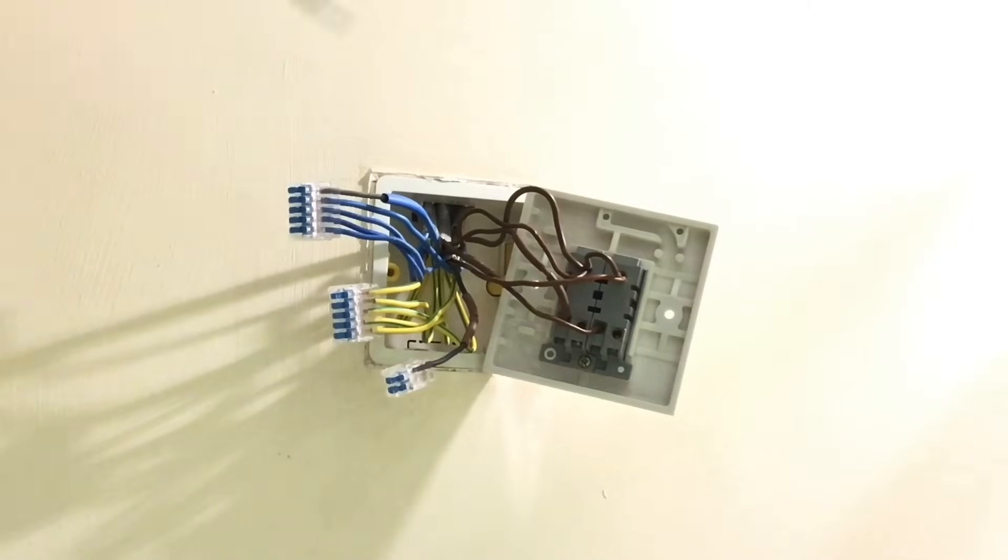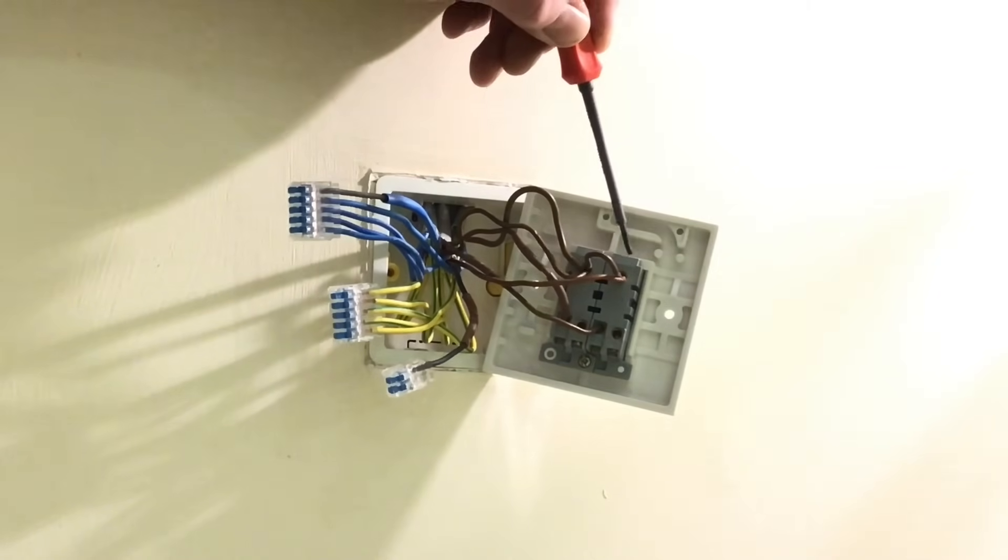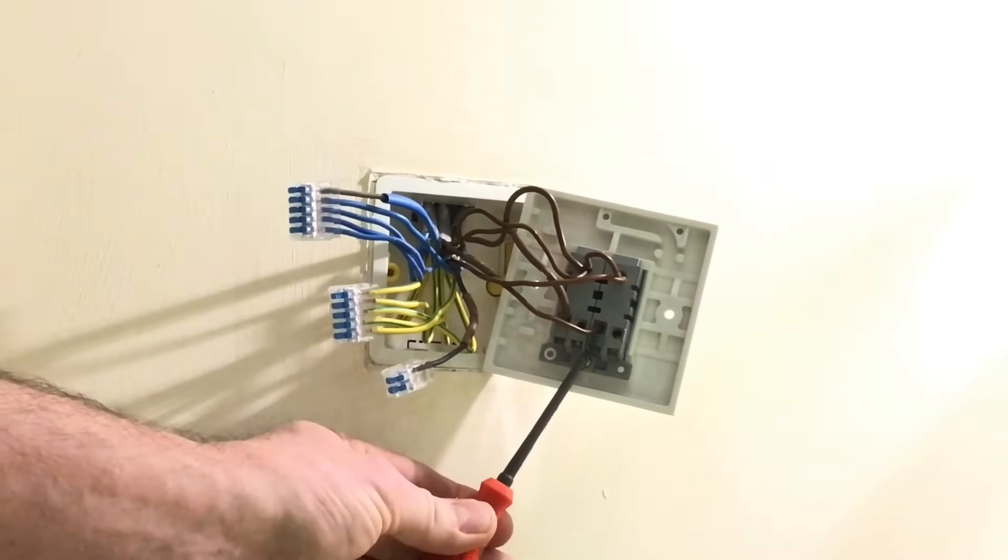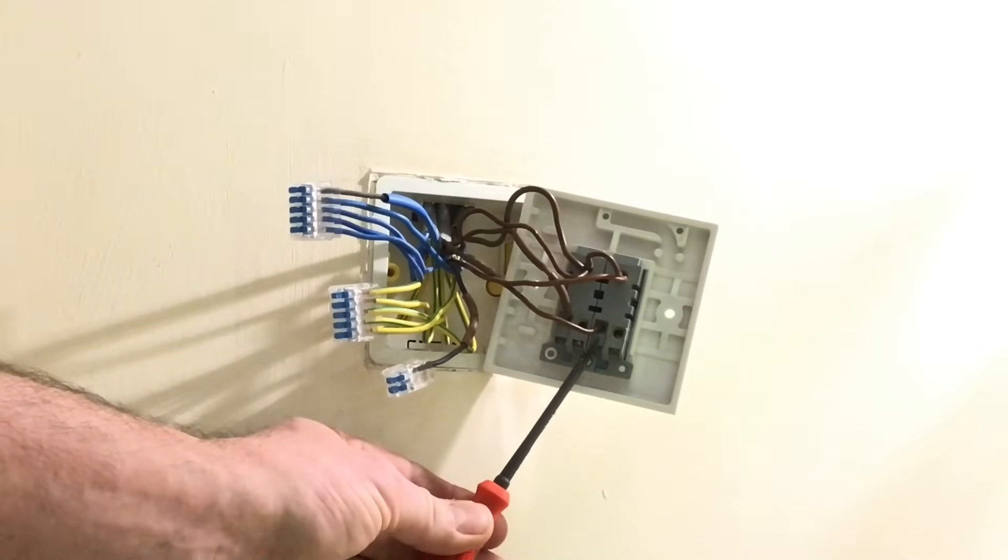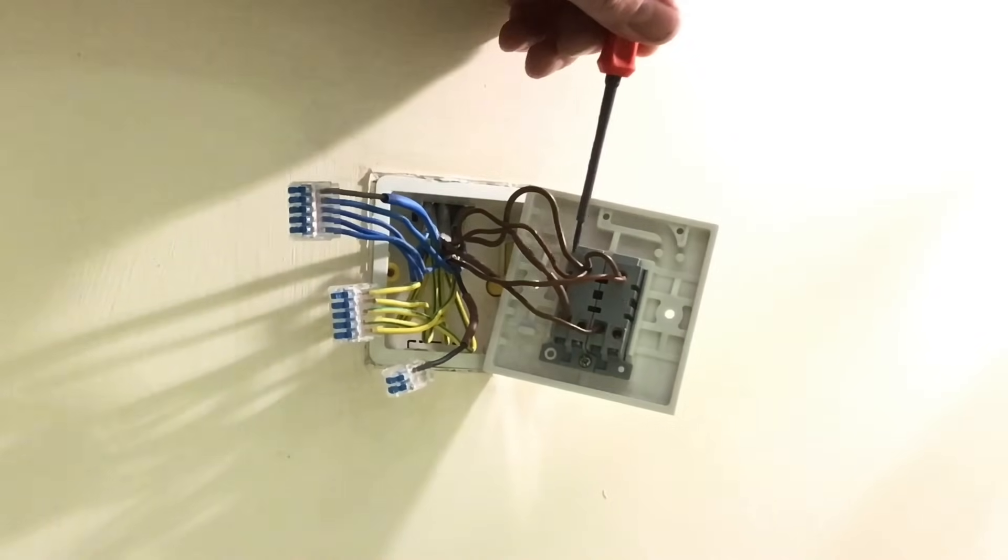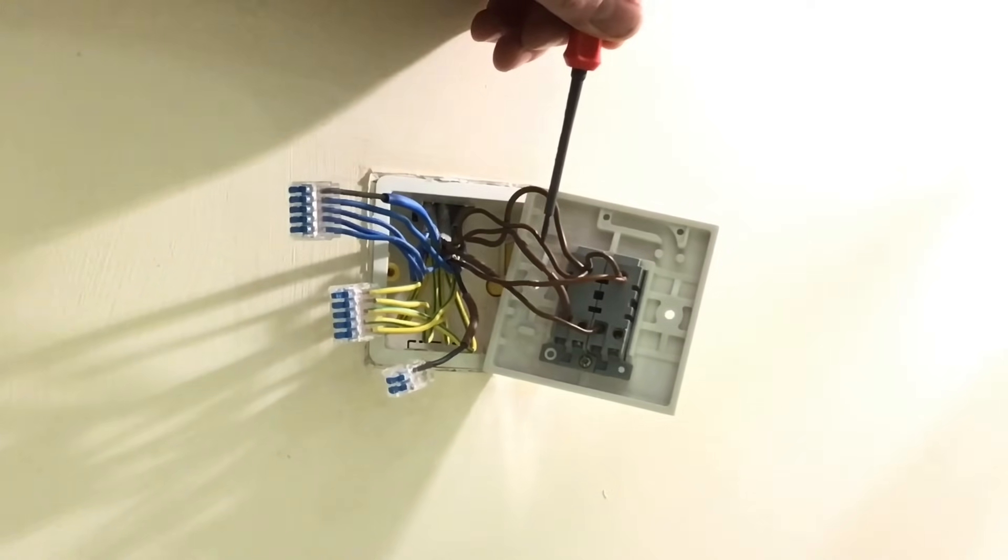Just to recap then, the feed comes into the switch and is terminated into the common. The permanent feed is looped across to the other common, of which there are two switching lines coming out, one for the spotlights, one for the pelmet lights. We've picked up from the same position here a permanent line to a 5 amp socket outlet for a TV, and a permanent line that goes across in a 3 core cable to feed another switch.